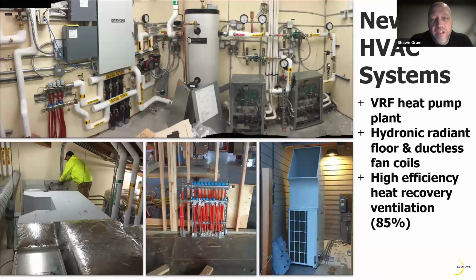Here's a little snapshot of the HVAC system. It's a heat pump system called VRF, variable refrigerant flow. They're quite popular these days. Up top is converting the VRF into hot water production, making water hot enough to heat a radiant floor. That's the primary heating, and then there are auxiliary fan coils. Just down on the left is a heat recovery ventilation system. This is a key piece of the load. A big portion of the load is heating the ventilation air. It's pretty much a year-round heating climate in Alaska, and so energy recovery ventilation is a great measure.